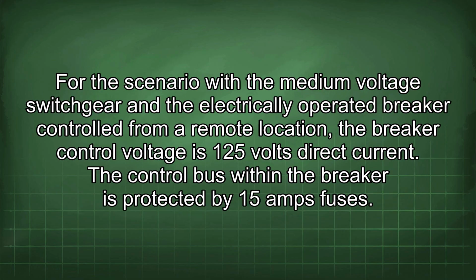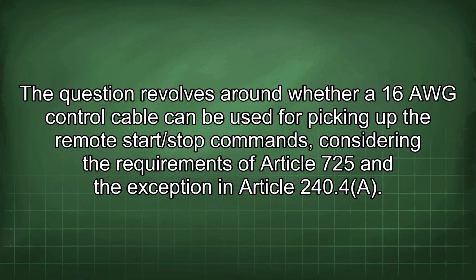For the scenario with the medium voltage switchgear and the electrically operated breaker controlled from a remote location, the breaker control voltage is 125 volts direct current. The control bus within the breaker is protected by 15 amp fuses. The question revolves around whether 16 AWG control cable can be used for picking up the remote start/stop commands, considering the requirements of Article 725 and the exception in Article 240.4(A).